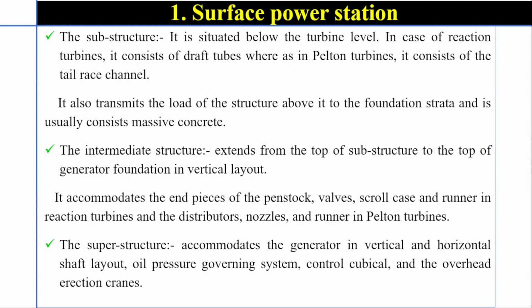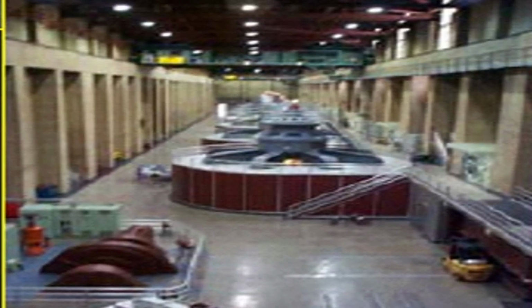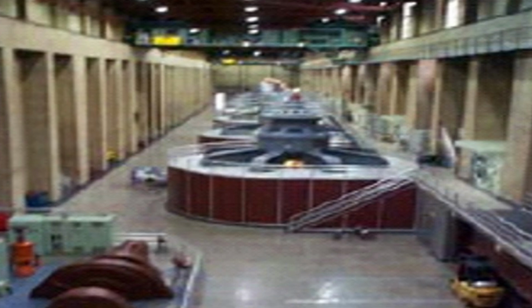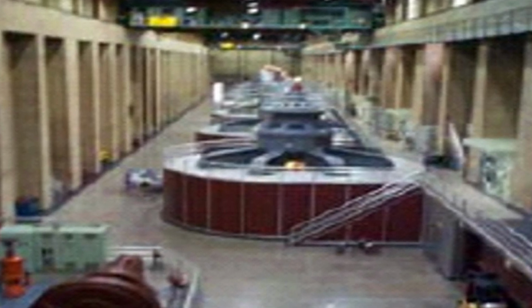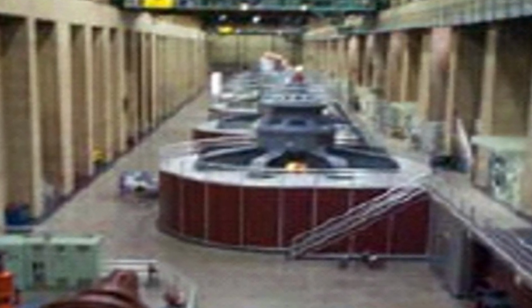Surface power station. The substructure is situated below the turbine level. In the case of reaction turbines, it consists of draft tubes, whereas in Pelton turbines, it consists of the tailrace channel. It also transmits the loads of the structure above it to the foundation strata and usually consists of massive concrete.